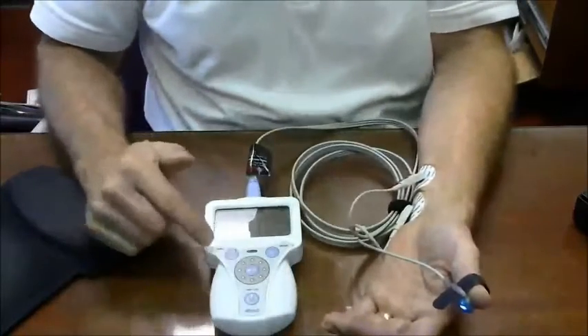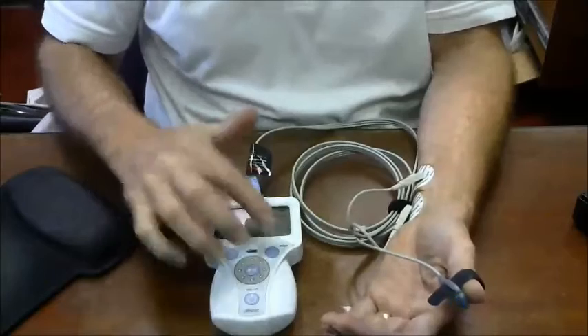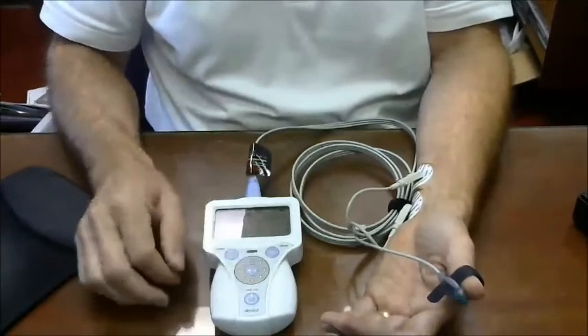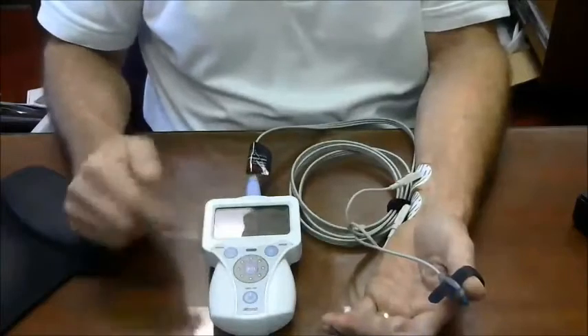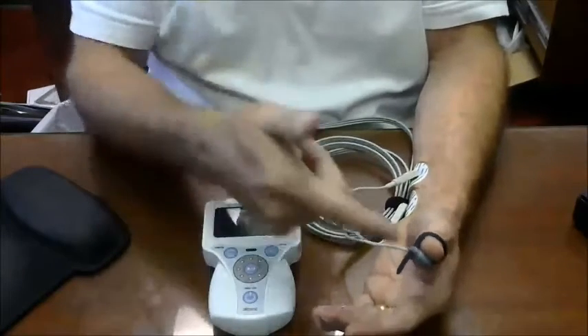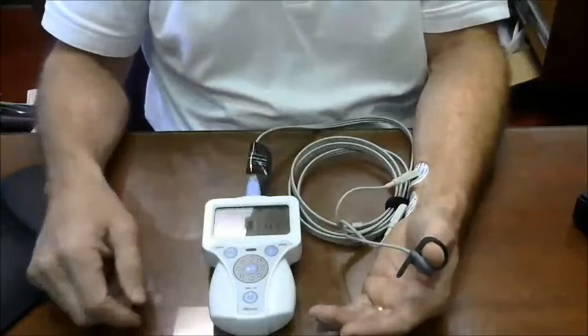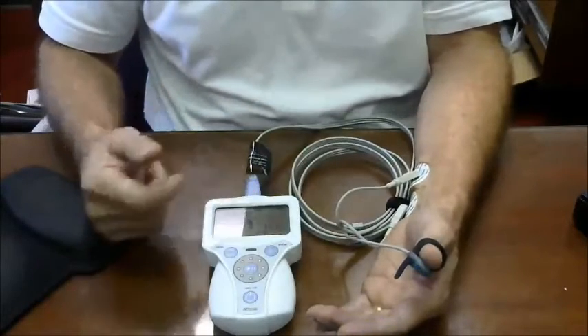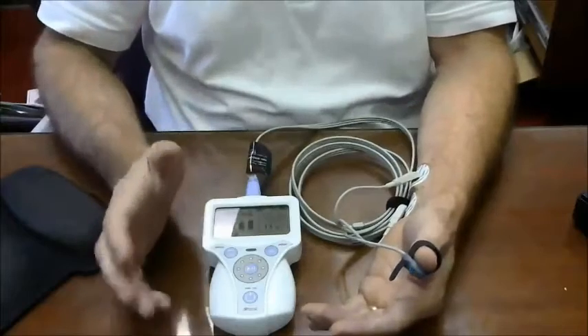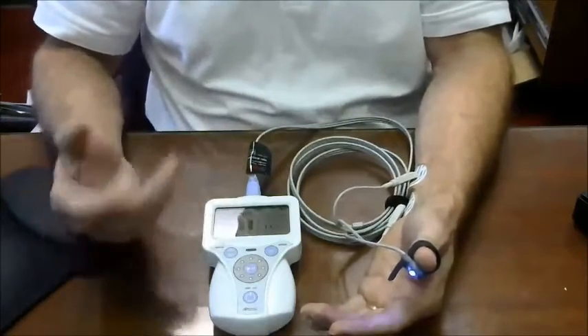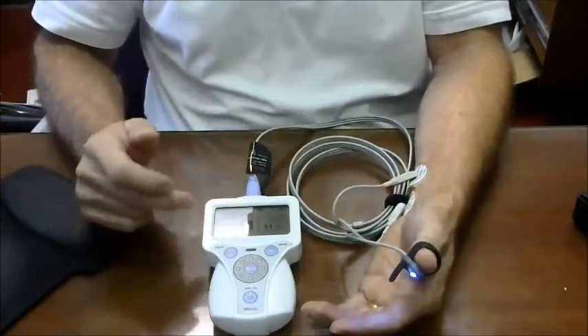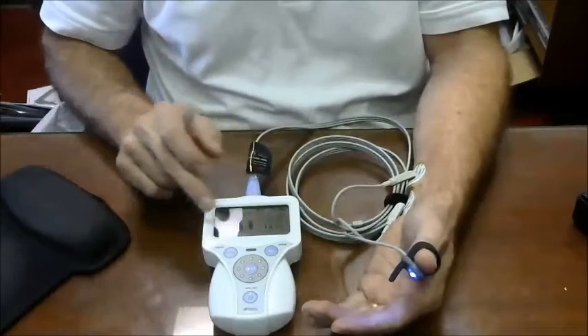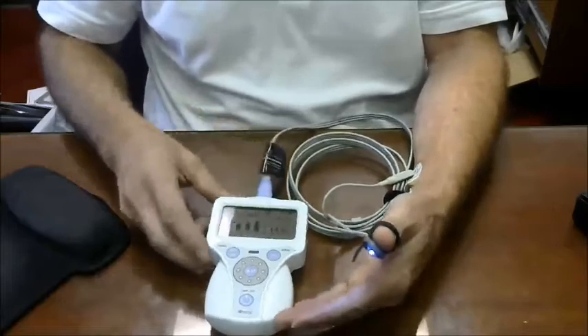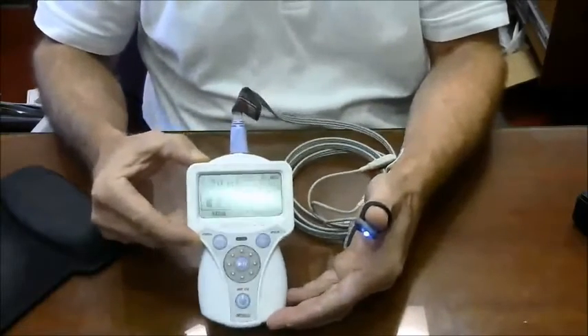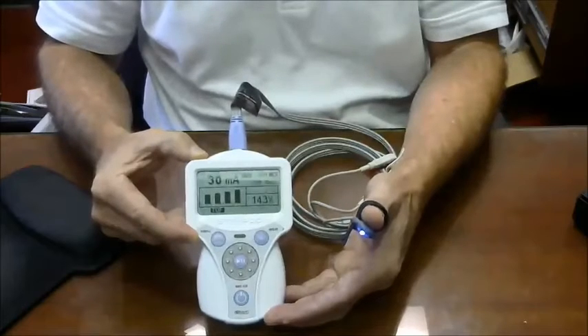So now I'm dialed up to 30 milliamps. I have the menu key that goes through all the different options and the enter key, but the middle key of the wheel is where I do my stimulation. If I press that, you'll see the green light goes on, and you also saw a green light over here go on, and you saw my thumb move. You notice it says that I'm 143%. Well, that tells you a couple things. It tells you that we do not truncate any information. We give you the information that it does. Basically what we're comparing is the fourth twitch to the first twitch. You can see even in the bar graph, hopefully, that the fourth twitch was much larger than the first twitch.